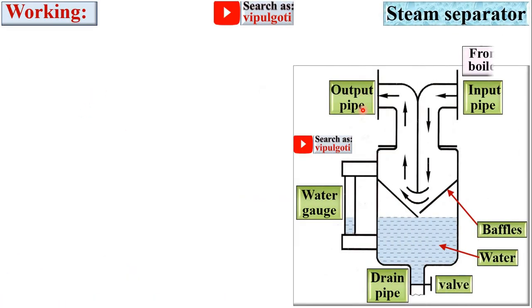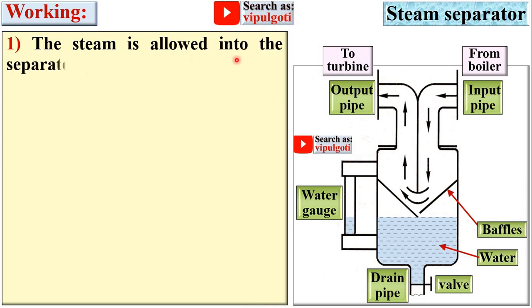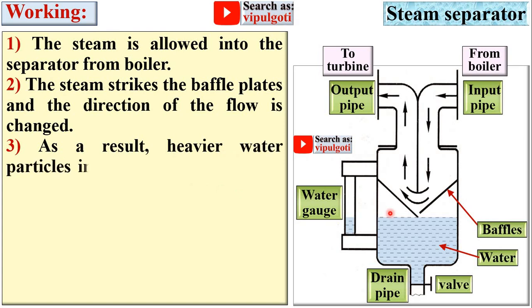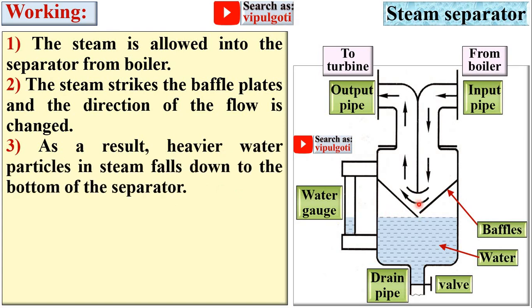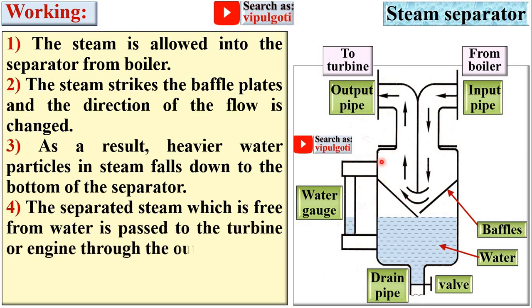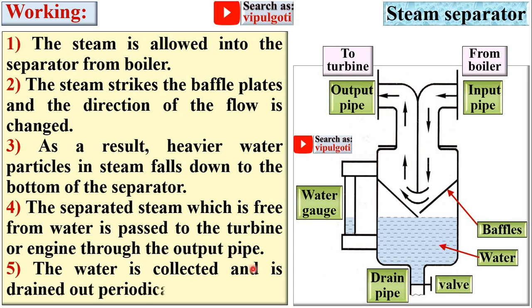Now the working of the steam separator. The steam is allowed into the separator from the boiler through this input pipe. The steam strikes the baffle plates and the direction of flow is changed. As a result, the heavier water particles in the steam fall down to the bottom of the separator. The separated steam, which is free from water, is passed to the turbine or engine through this output pipe. The water is collected and drained out periodically with the help of this valve.